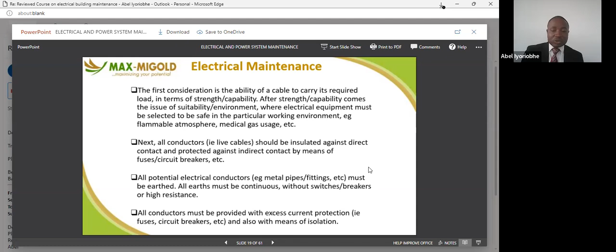So testing, why do we need testing in our installation? We need testing so that we can be sure the installation is fit for anybody to use. If you carry out tests and ensure you document it, it gives you a close relationship with your installation. You know when a problem occurs and when to carry out the next maintenance schedule. So testing of your installation, like your earthing system, continuity test, open circuit test, they are very important in installation. I know most of us are doing this.